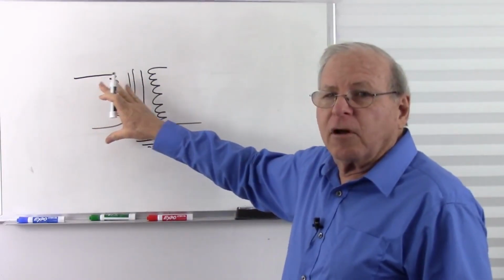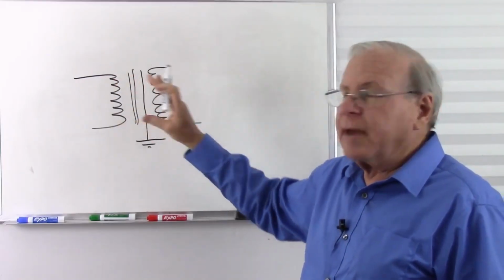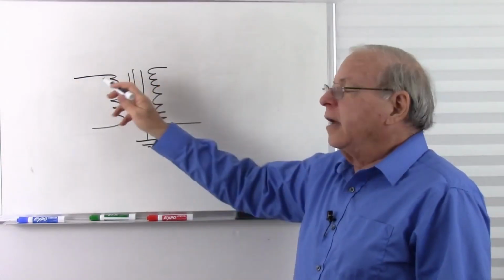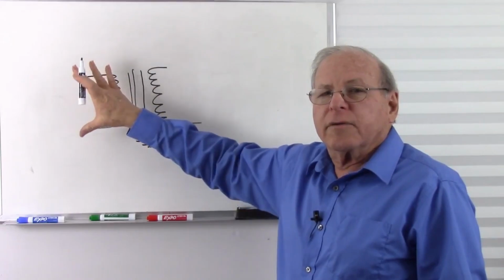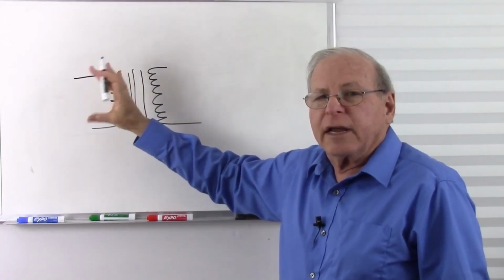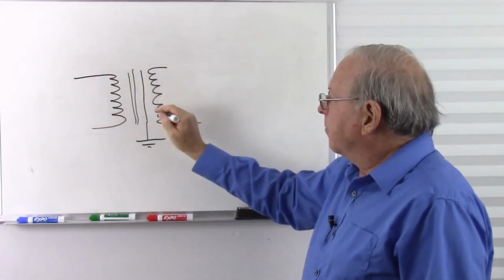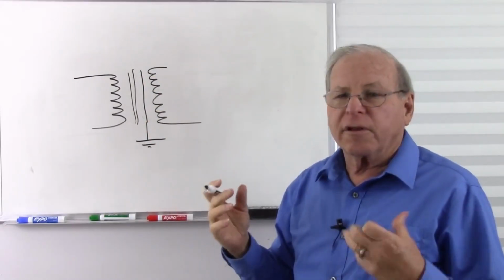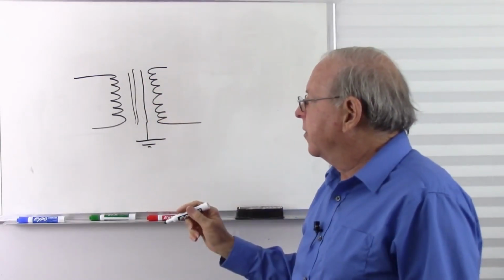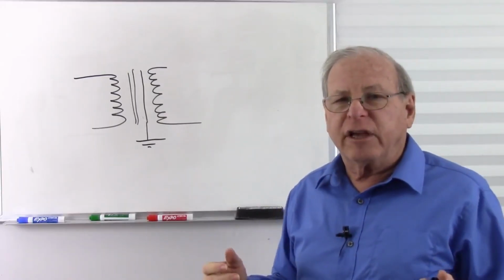All of the coupling, all of the energy goes across through moving magnetic fields. And if we get any high frequency currents going over here that tend to create electromagnetic radiation, that will be stopped by that foil shield, which we call a Faraday cage, that's wrapped around the secondary. So that's the construction of an isolation transformer.